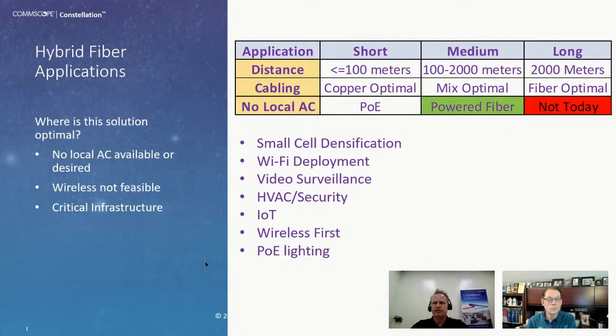Now medium distances, between 100 and 2,000 meters—typically what we're doing with cable installs is a mix of copper and fiber, star topology, bringing fiber to TRs and distributing it through different floors. It's a good mix of the different types, but powered fiber allows you to cover the medium distance and include remote power.